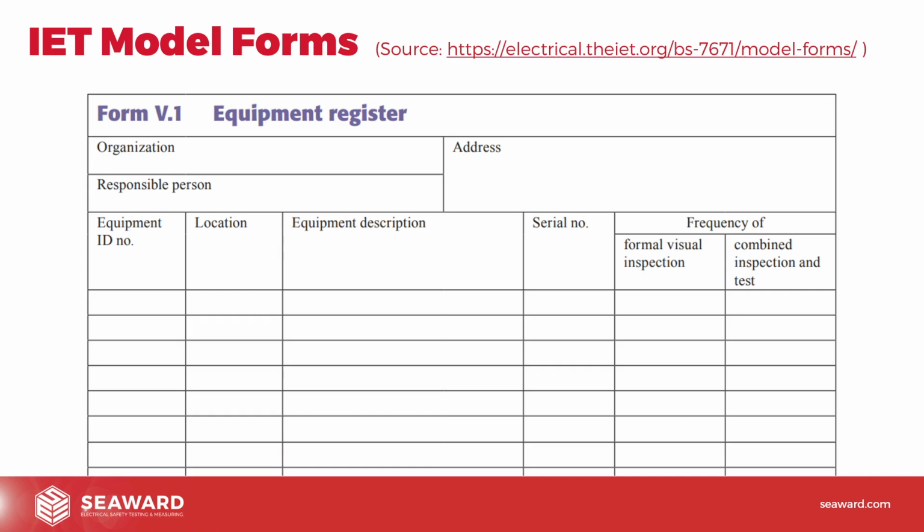But also, the manufacturer's serial numbers might be about 20 digits long or something like that, and you've got to try and put all that data in and keep it correct, and there's room for errors. So people do tend to number equipment, but you need to come up with it. Generally, a numbering convention is good. So you might decide, right, we're going to go with 5 digits. It's all going to be numerical. So we just start with 00001 or whatever it is, and number 2, number 3, number 4, and we go through.